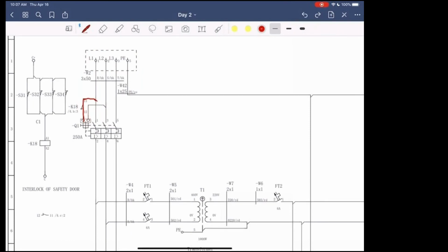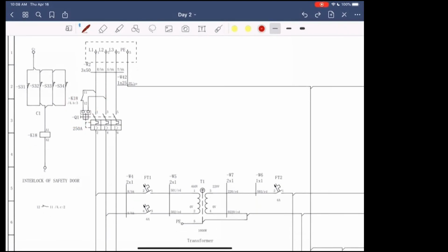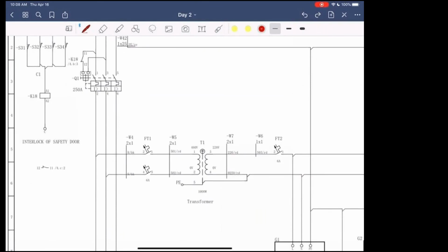So when working on the electrical end of this machine, you have to be extremely cautious about these two wires, because it is 480 volts and you will feel it. You just have to make sure that you don't touch those wires without the power being cut off at the source. This disconnect is a 250 amp disconnect.